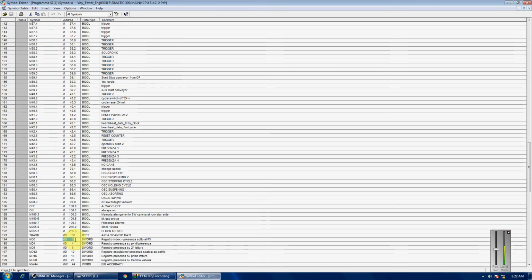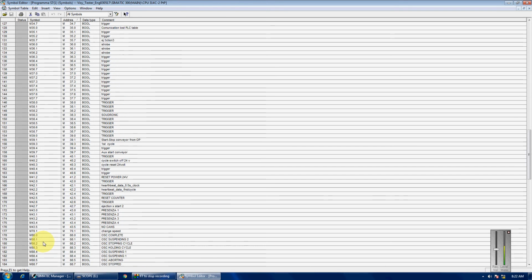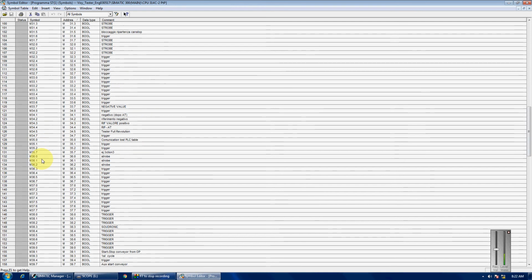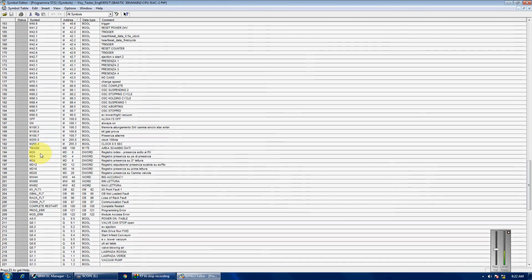This one's taken up 4 bytes, so they're accessing the whole 4 bytes, but they're also accessing the 7th bit in that whole thing separately. So you can get really caught out. You say, oh, they're only using bit 7, I'll use bit 1, bit 2, if you look at this list. But they're actually using the whole double word, which is why I got you to go to reference data and said stay away from the blue bits.